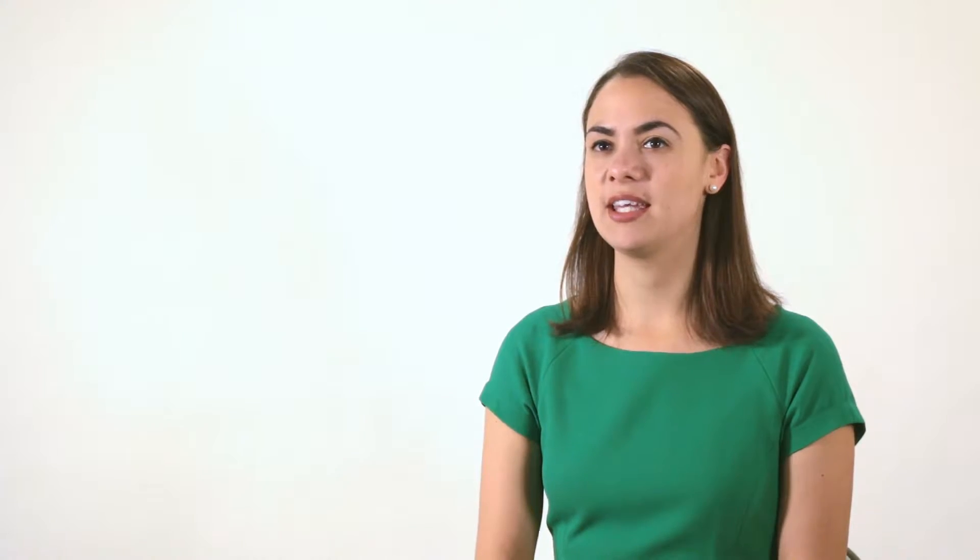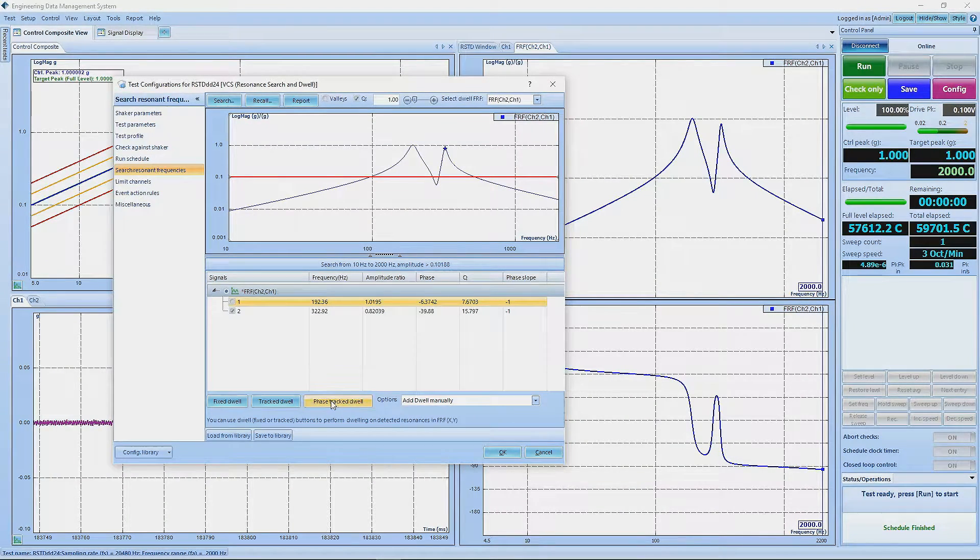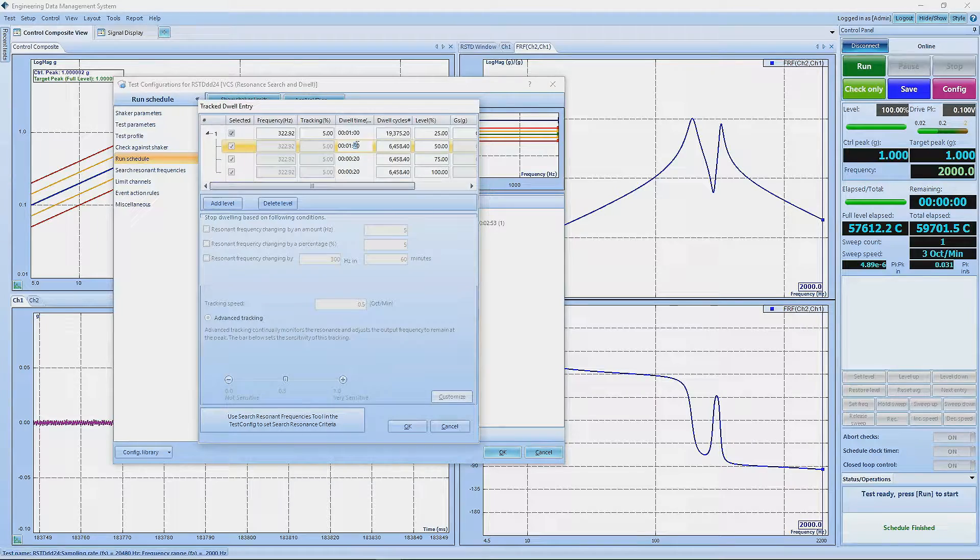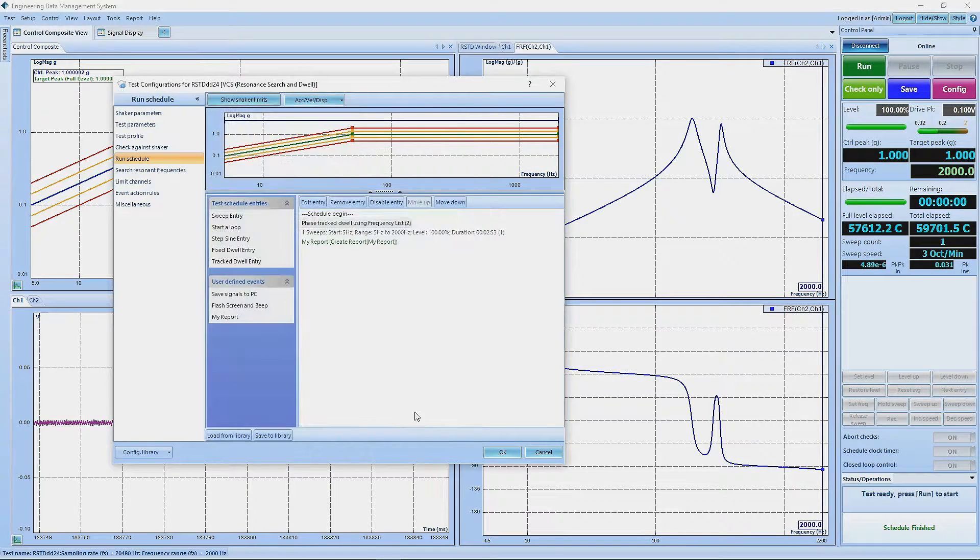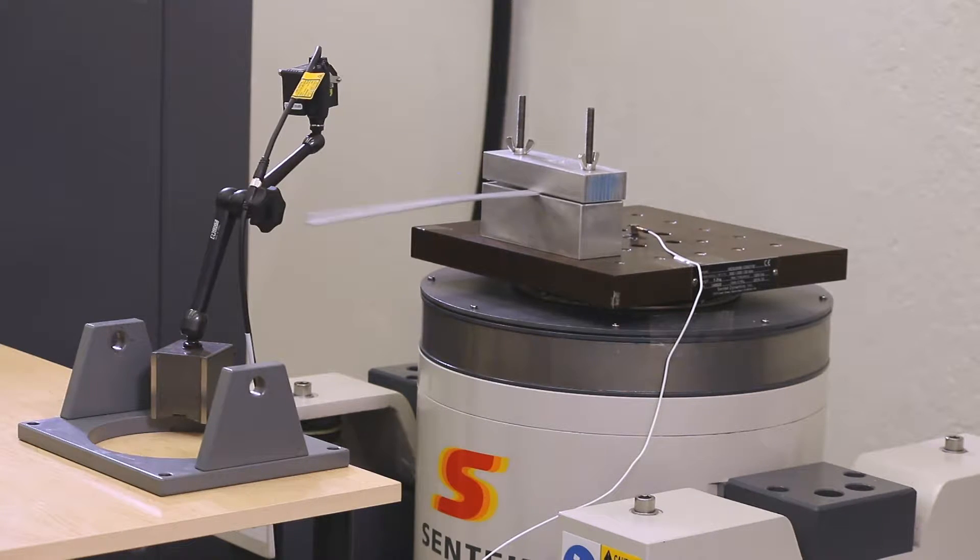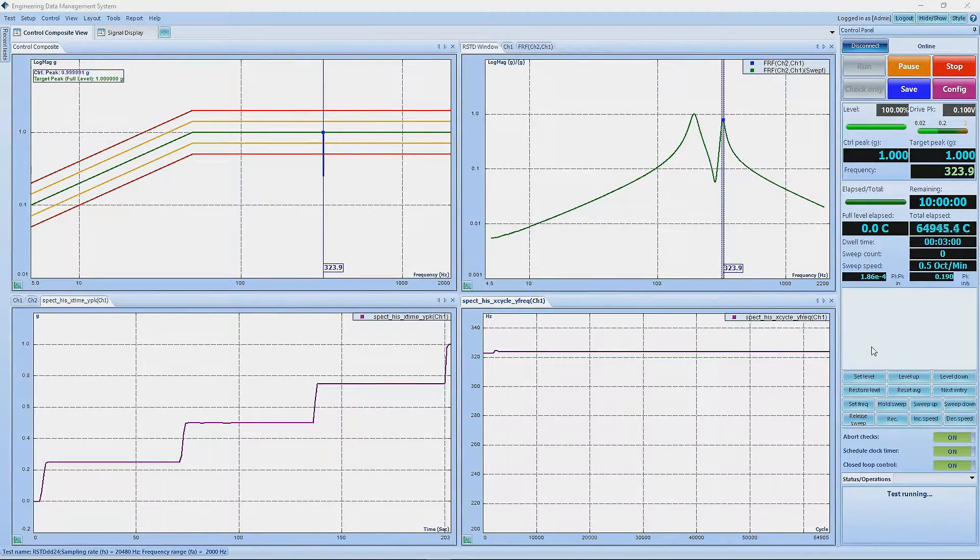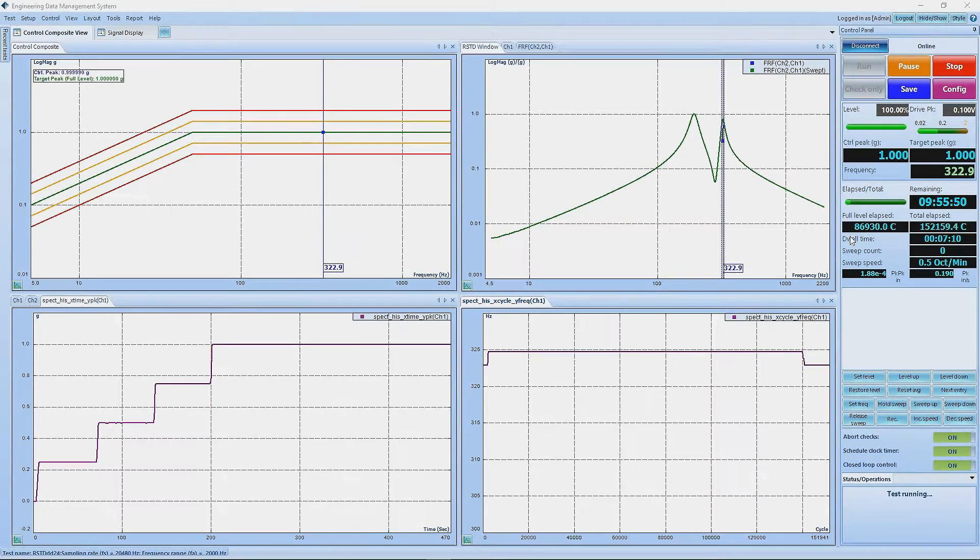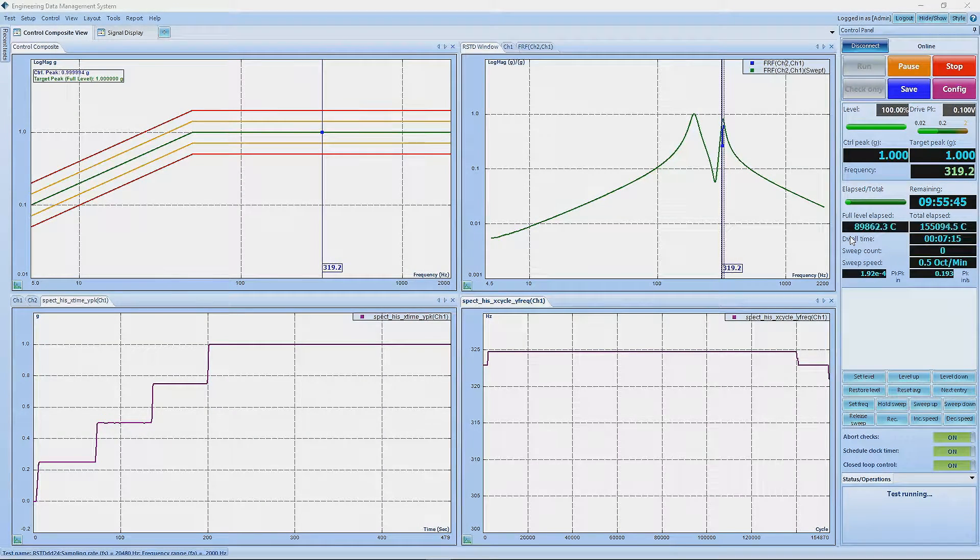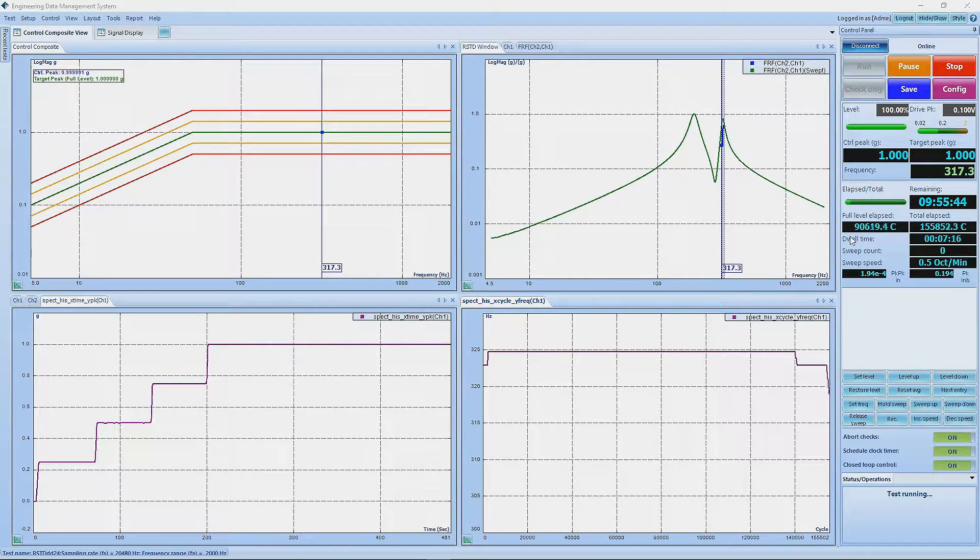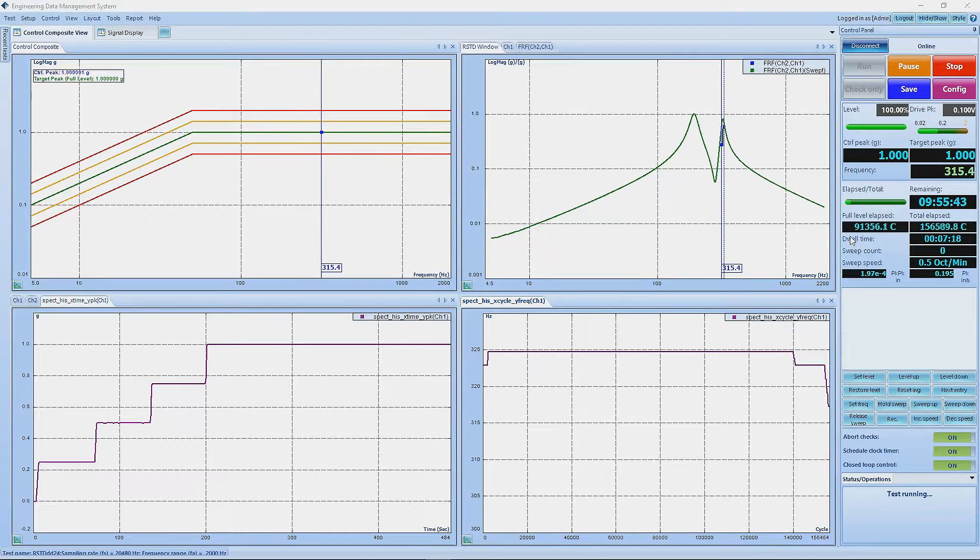Crystal Instruments developed phase tracking to track changes in a device under test resonance as that resonance changes during the test. The amplitude and phase can be measured continuously and accurately. The vibration frequency can also be finely adjusted to ensure that the material is consistently vibrated at its resonance frequency until a steep change in amplitude signifies fatigue.